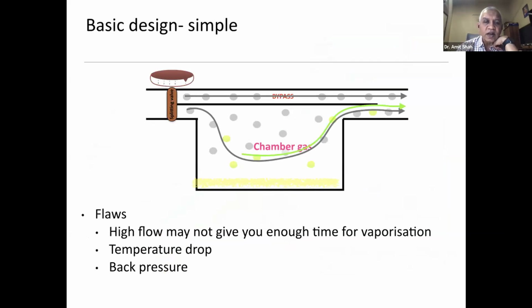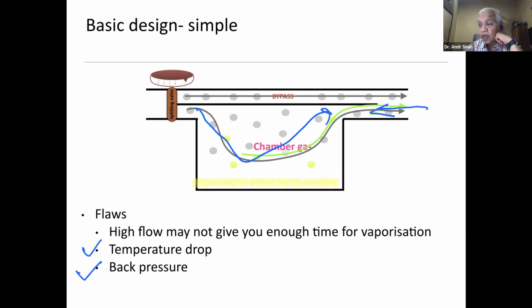Now you just realize that a lot of gas flow passes through this particular chamber, in this vaporizing chamber. Now there are three things that happen. One, the temperature will drop because it will take the agent, the new vapor will form, so the temperature will drop. Sometimes when you give positive pressure, a back pressure can come back from here. That will also have its influence.